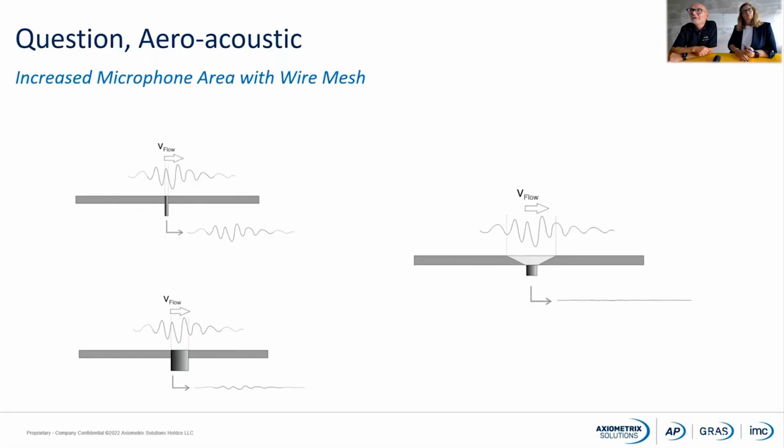If we use a turbulent screen, where we have a big screen, which we could call a first diaphragm, and then a little bit below that screen we have the microphone itself we are using for the measurement. So we average over this big screen, and we will get rid of the turbulent noise, but we will still be able to see and hear the acoustical noise.